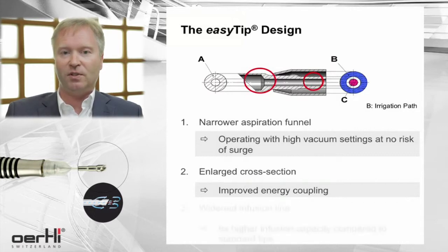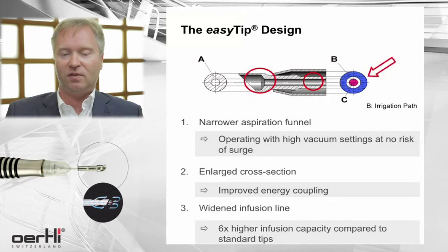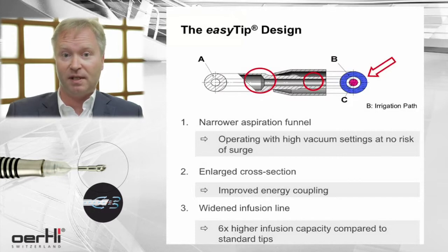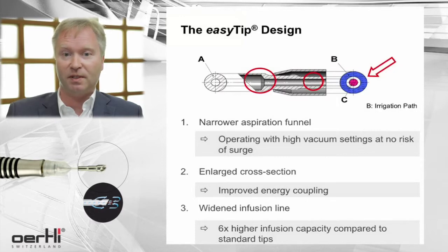The third change is related to the infusion line. Given that the aspiration funnel has been made narrower, there is more space now for the infusion line, giving you a high infusion capacity which is around six-fold higher than compared to standard conventional tips.